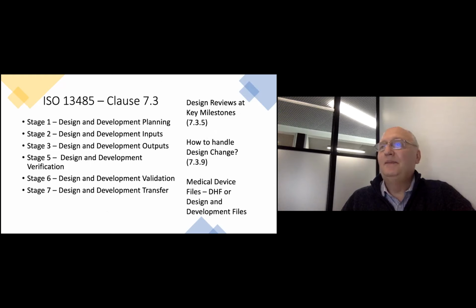Design transfer is a bit more complicated, or it's a bit simplified for software. It's how you deploy your software, how you take it out from the development environment and put it into the release process, right? Because software tends to be easy to distribute, right? Okay, and intermingled into that are key stages for design reviews at user requirements, design inputs, design outputs, at the end of the verification and validation stage, and at the end of the deployment stage. 13485 also asks you to have a medical device file or design history file.